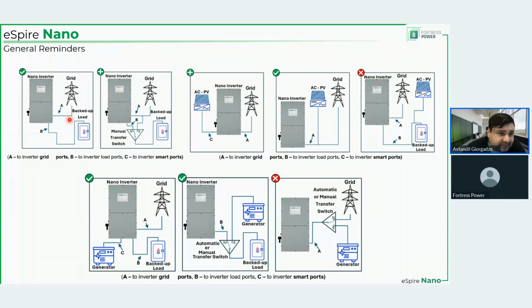In this case, if something is to happen to an inverter, and let's be honest here, any man-made object can develop some kind of a problem preventing it from operating normally, you have no way of delivering grid power to the backed up load, although grid would be available and the backed up load would require that power. So we recommend using a manual transfer switch. The manual transfer switch with emergency port will connect to the grid upstream of the inverter. And the load port downstream will be connecting to the normal port of the manual transfer switch or bypass switch, however you want to call it. And the load will be connected to the backed up load.